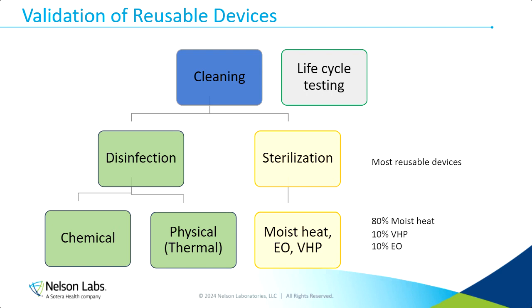Now, when it comes to reprocessing validations, what we're validating is these processes. We're validating that the cleaning can remove that visible contamination, that the disinfection can achieve that specific log reduction, and that the sterilization can achieve that sterility assurance level. And it's important to note that these processes need to be validated separately and independently of each other. Combination testing typically is not allowed, though it may be appropriate in some cases, which we'll talk about a little bit later today. But for the most part, these processes will be validated separately and independently of each other.